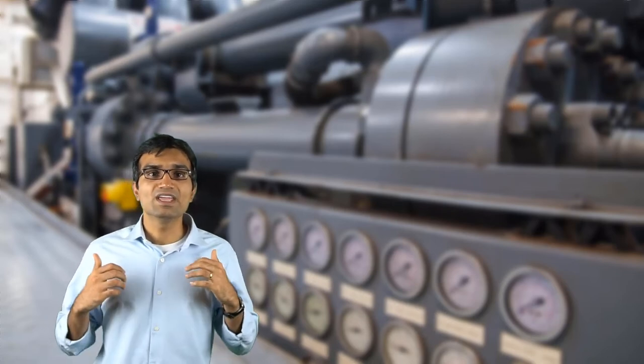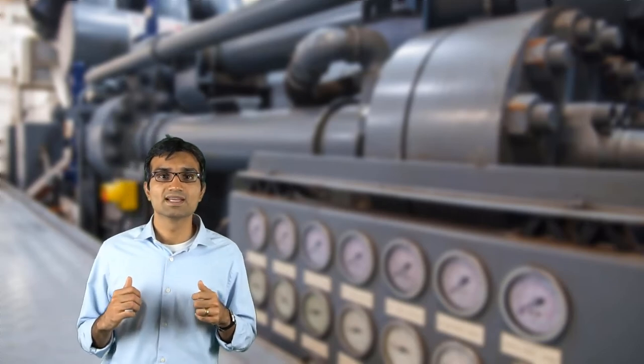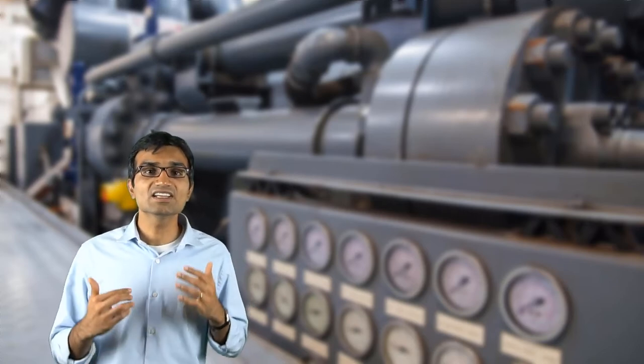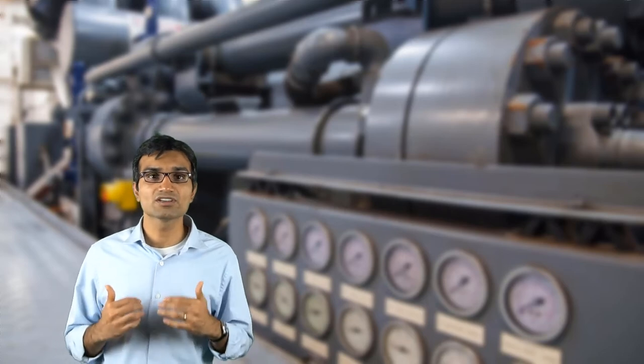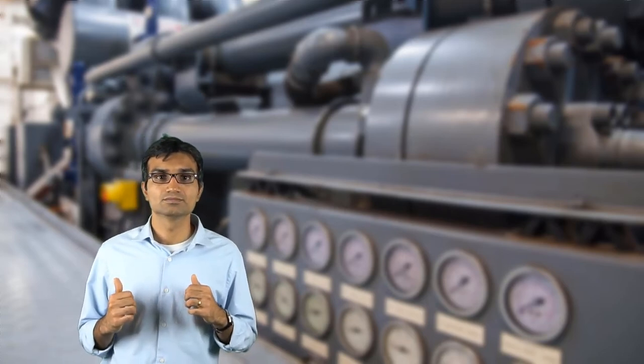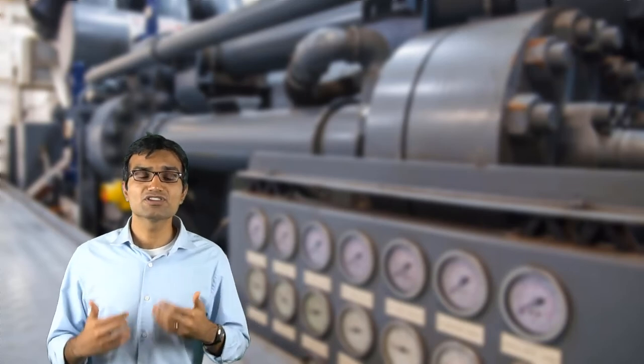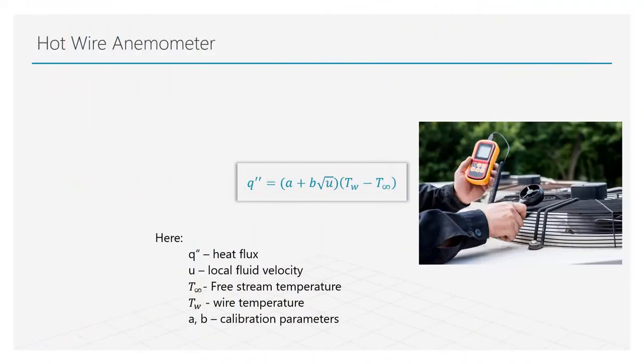Hot wire anemometer is another intrusive way of measuring the local velocity in the flow field. In this method, we insert a thin long wire into the flow. This wire is electrically heated and attempts to measure the local flow temperature. Based on the overall heat flux and the temperature difference between the wire and the fluid, a local velocity is calculated. This method, however, makes use of carefully calibrated coefficients to estimate the local velocity of the flow.